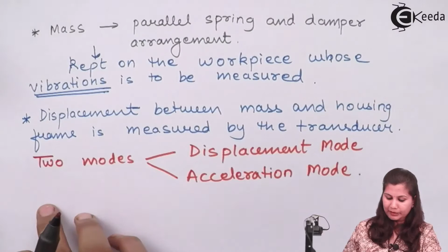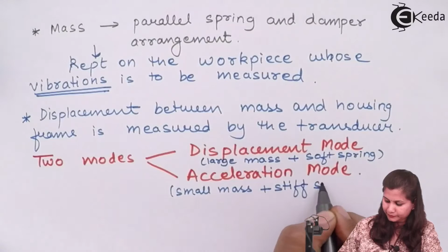The difference between the two modes is the type of spring and mass used for the measurement. In the displacement mode, a large mass and a soft spring is used, whereas in the acceleration mode, a small mass and a stiff spring is used. So for the displacement mode: large mass plus soft spring. Whereas in acceleration mode: small mass plus stiff spring. That is the difference between the two modes.